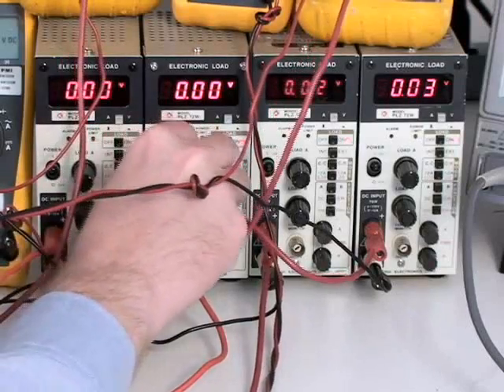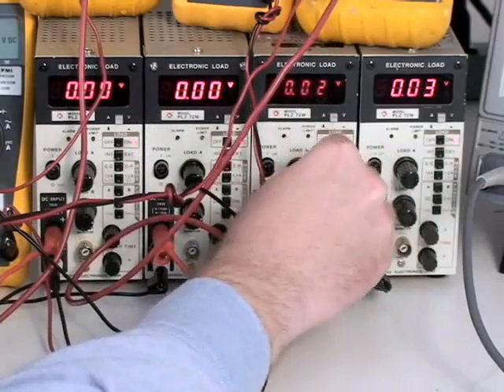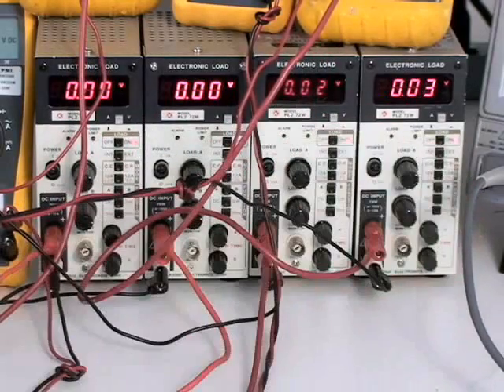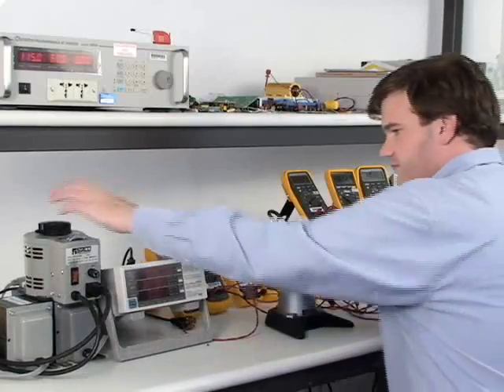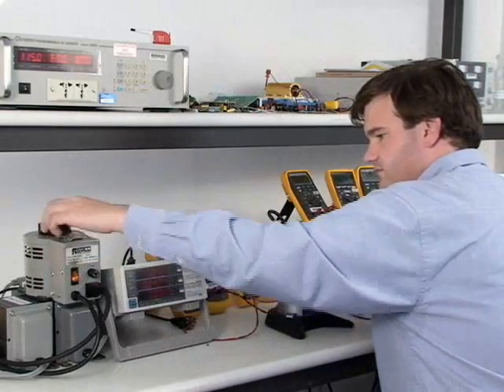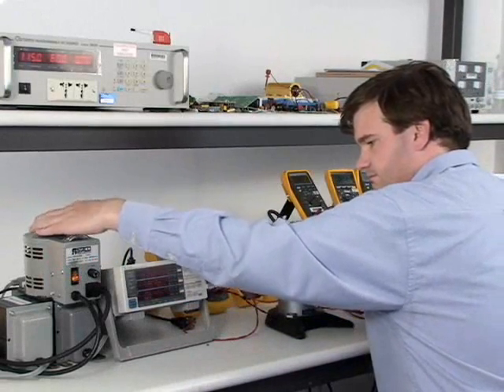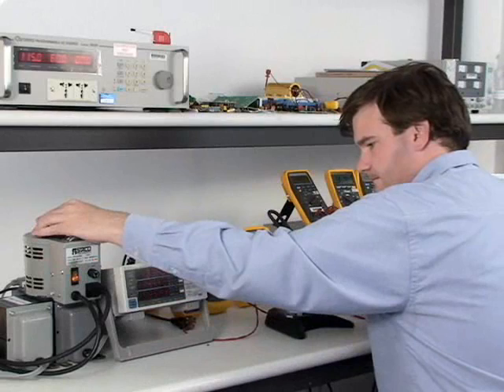Set all loads to draw a small amount of current from each output to prevent peak charging. Again, zero the AC input, turn it on, and slowly increase the input to the minimum operating voltage for your design.